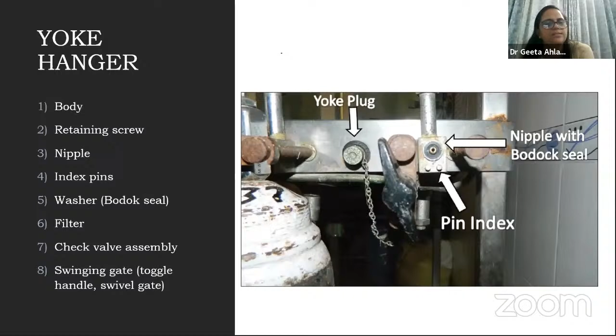So another important feature on a cylinder is the pin index. So what is a pin index? It is a marking on all the cylinders. It is a conventional safety system where, 12 degrees apart, in an arc of 60 degrees, places 1 to 6, as you can see on my screen. 6 points are marked at a difference of 12 degrees each, which have been conventionally allotted to various cylinders as depicted in this table below.